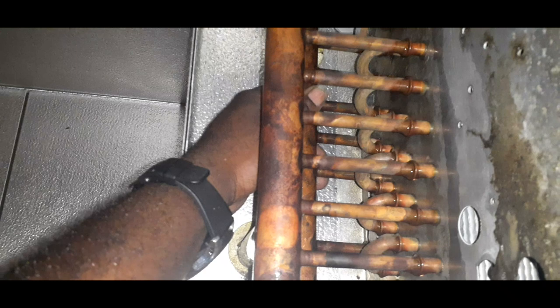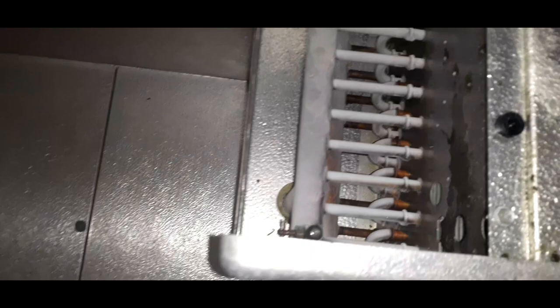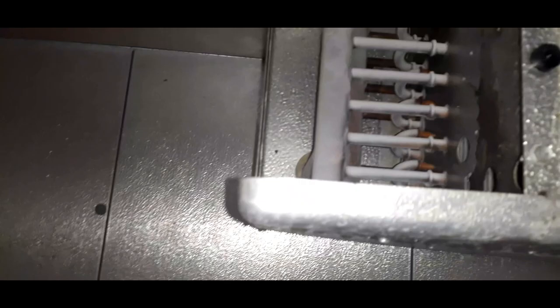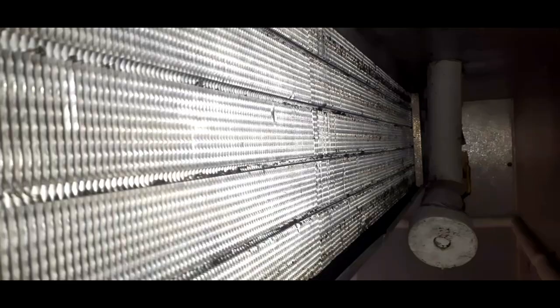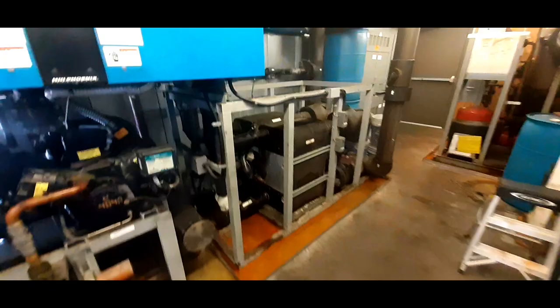All right, so this pipe is not cold, so it does seem that the solenoid is working, stopping the flow of glycol. Let's go ahead and flip the switch and see what happens. Let's turn this on, system 39. All right, so you can see my pipe starting to ice up. That solenoid is working, it is holding. As you can see now it's starting to frost up. If it didn't work properly, what would happen is it would continue to frost up the whole time I was de-icing the coil. All right, so these valve coils are all clean.